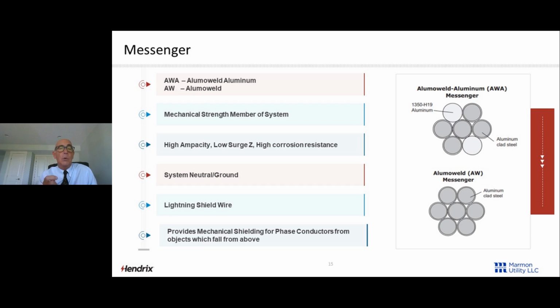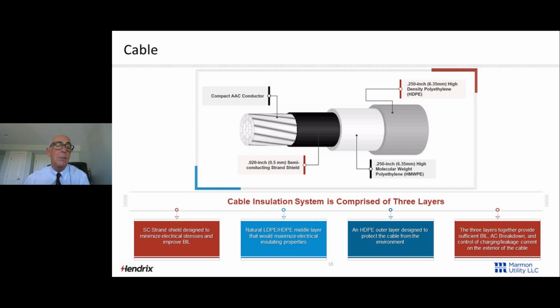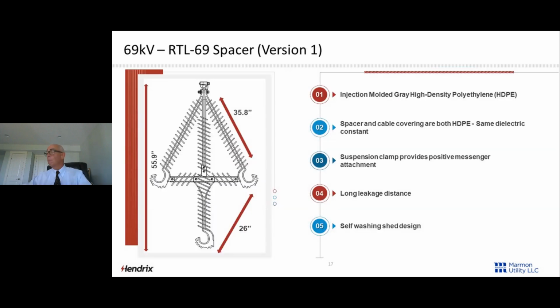Because we're using Alumoweld aluminum, it has a high ampacity. It has a low surge impedance, and because we started using it in coastal areas and industrial areas, it has a very high corrosion resistance. You're not going to rot out a steel core. It's coated. And again, as we said before, it's a system neutral, ground, lightning shield, and it provides protection for the phase conductors above. And it's the same conductor we just discussed moments ago.